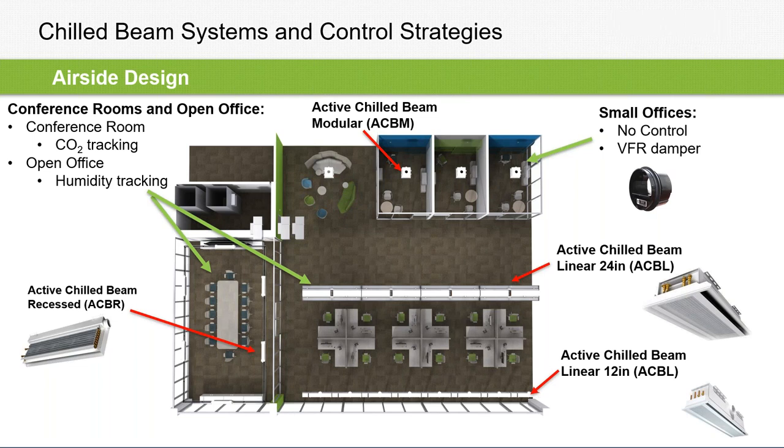So essentially, yeah, I think Ed's got some comments to make here too. But that's really a temperature controls question. The beam is a pretty simple device. It's a coil in a box with a valve. And the valve is basically controlled by the building automation system. And we can make beams super smart if you have the right control sequences associated to it.